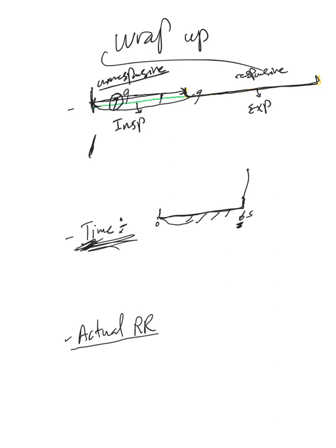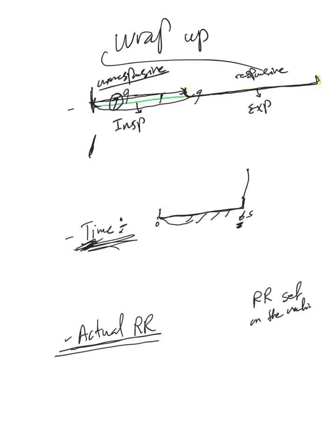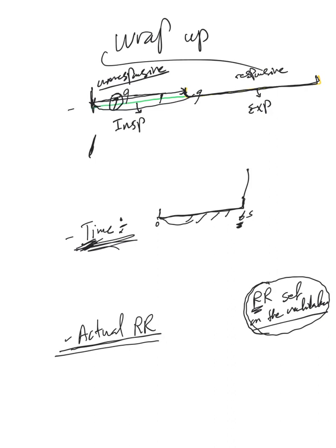Actual respiratory rate means the respiratory rate that the patient is having right now, and it can be different from the respiratory rate set on the ventilator settings. That's the minimum number of breaths that the patient will receive, and this is the actual respiratory rate.